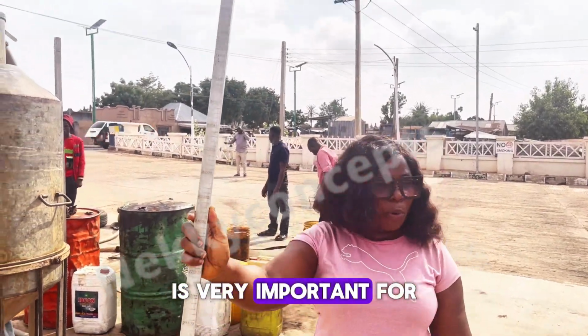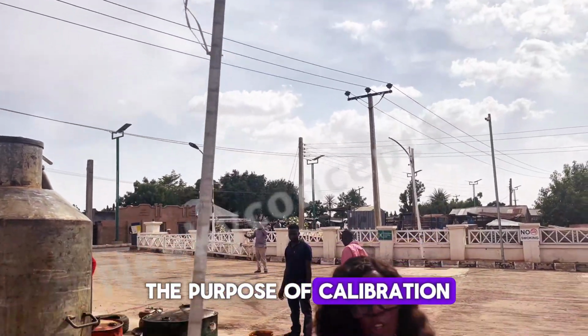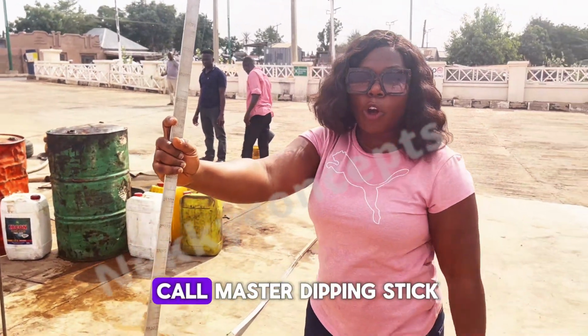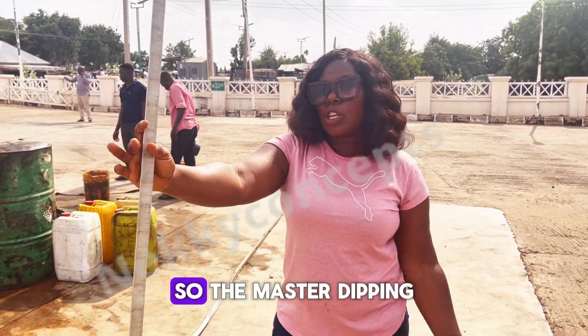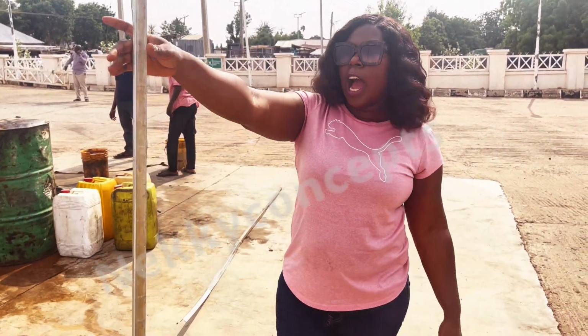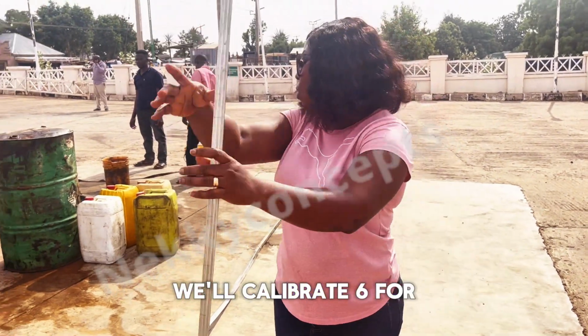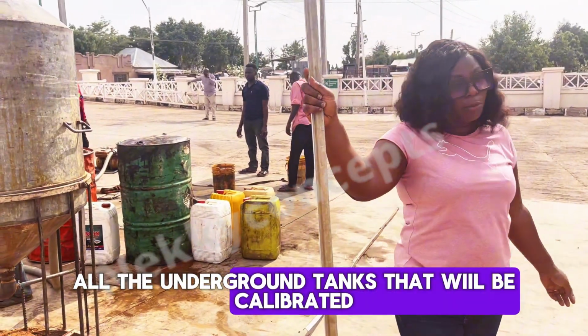It's called a dipping stick. The dipping stick is very important for the purpose of calibration. For this process, we'll use what we call the master dipping stick, and at the end of the day, we'll calibrate sticks for all the underground tanks that will be calibrated.